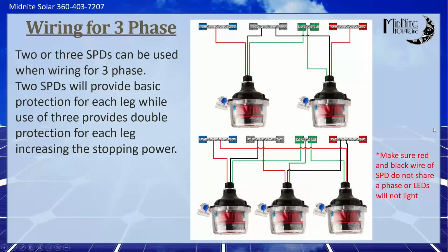Three-phase is another one we get questions on, not quite as often, but we do get questions quite a bit on three-phase. You can do it with either 2 or 3 as shown. And this is going to be recorded. You guys can get a copy of this so you don't have to take pictures or whatever. But if you're doing 2 on three-phase, then you do one leg of SPD 1 to phase 1, one leg of that SPD 1 to phase 2. The second SPD, you'll go to phase 2, and then the second leg of that will go to phase 3.